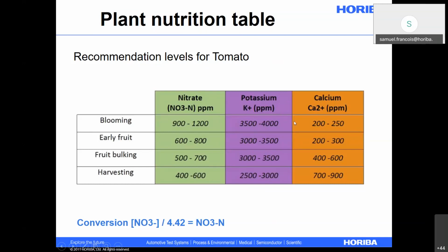So first, it's important for you to understand that from 0 to 99 ppm, the step is one by one. So for example, 45, 46, 47. When the meter goes above 99, then the step is 10 by 10. So for example, 110, 120, 130. And then when we are in the 1,000 range, the step is 100 by 100. So 3,500, 3,600, 3,700. Usually the range is pretty wide, like 500 ppm, or sometimes even wider, more than 1,000. So in agriculture, it is not so important to have such a precise measurement.